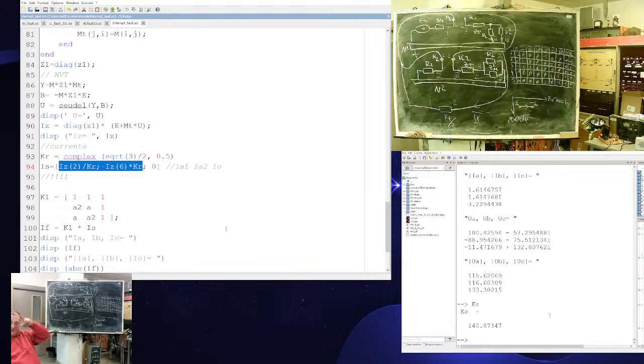I'm introducing a phase shift by 30 degrees backward for the direct sequence and forward for the negative sequence, because the transformer has the 11th group. If it would be the 12th group, there will be no shift. If it would be the 5th group, I should go forward for direct sequence and backward for negative. But this one is typical 11. So backward 30 degrees for direct sequence and forward 30 degrees for negative sequence.